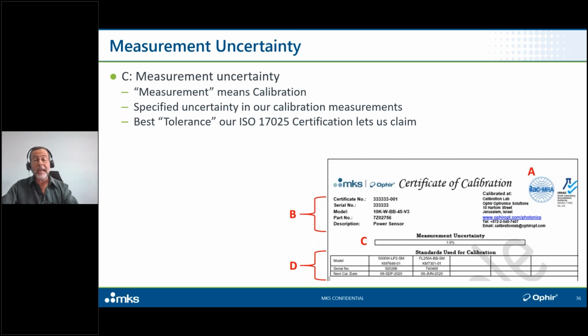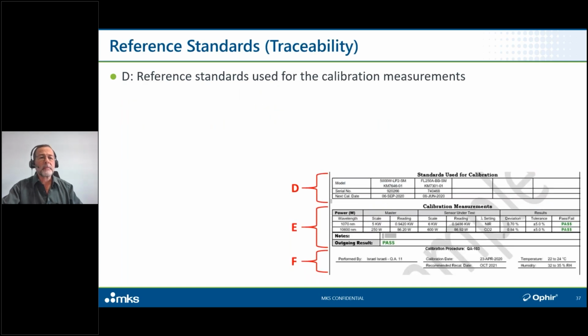So the answer to the question, how far off of the absolute truth is this sensor? The answer is not a single clean number, but it's a probability distribution about some number, as we said a bunch of times earlier. Calibration uncertainty is important. The measurement uncertainty, as we call it here in the document, is important for deriving pass-fail criteria to determine whether a device meets its accuracy specifications. And if you want to know where does this measurement uncertainty value that we write here come from, then for that, I refer you back to that white paper on our website, which goes through all the numbers and all the calculations. Oh, just one thing I forgot to mention.